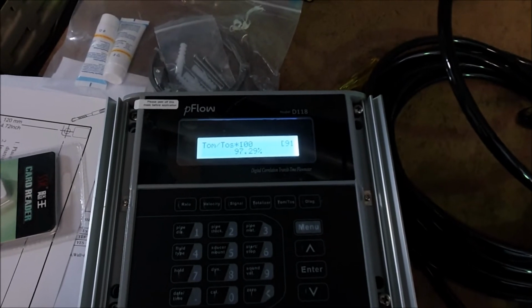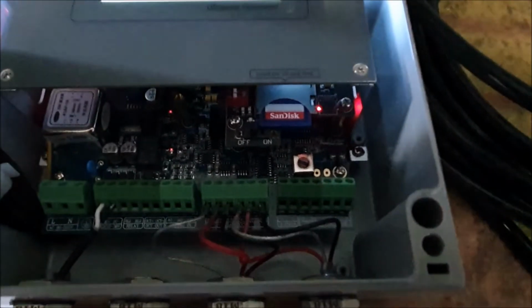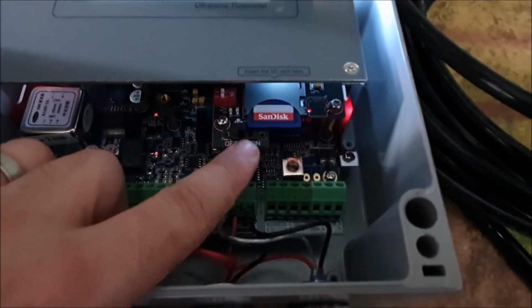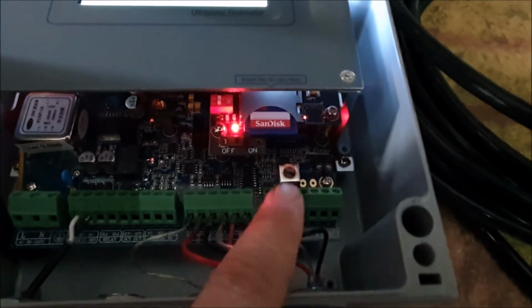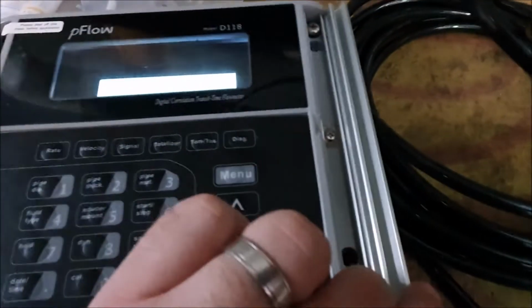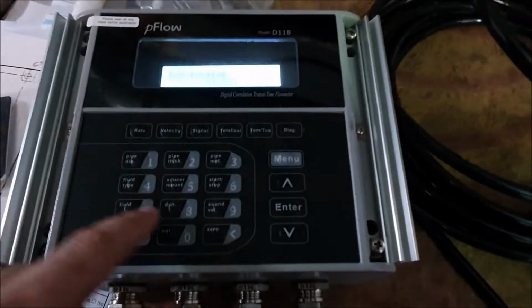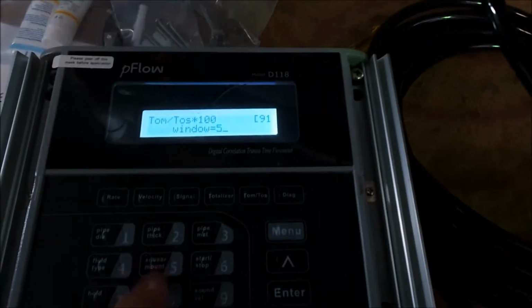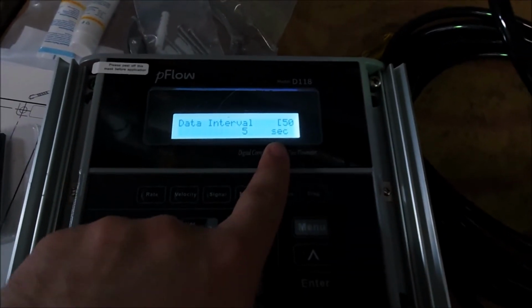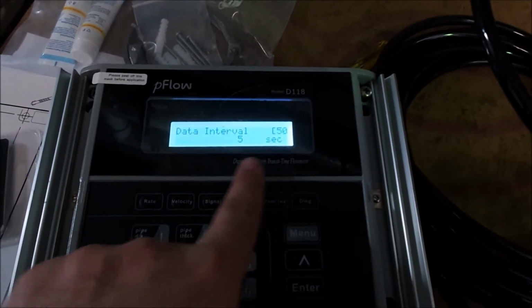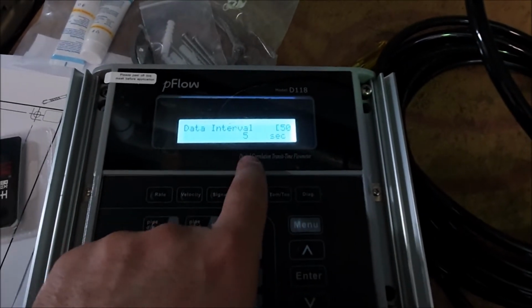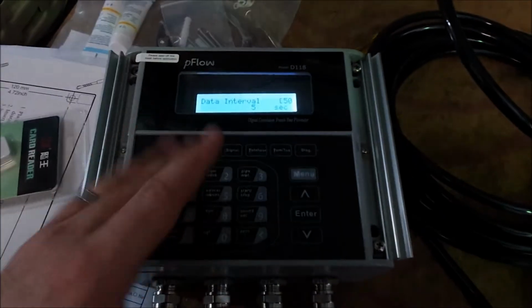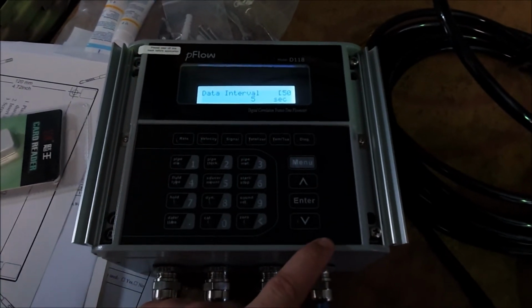Perhaps logging. So you'll see inside the flow meter you've got an SD card. This is for your logging, and there's a switch here in front of it as well. It's got off and on. So if you want it to be logging, just have the switch in the on position, and you can set how often it takes a log. That's on menu 50. So if I go to menu 50, it's got data interval. You can change this to how often you want it to take a log, and each time it hits that interval, it'll store what the flow meter is reading onto the SD card.